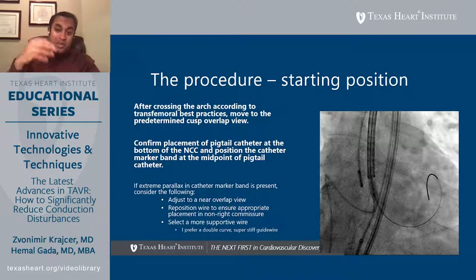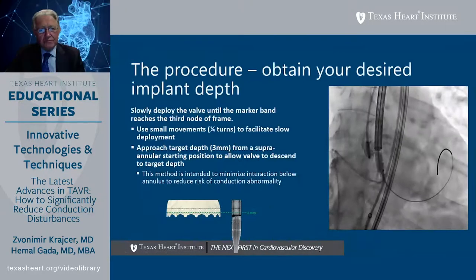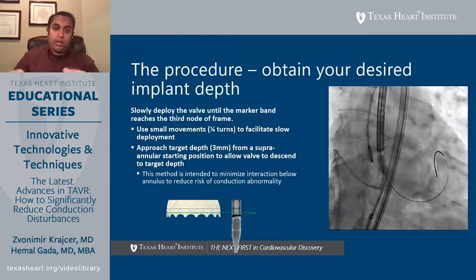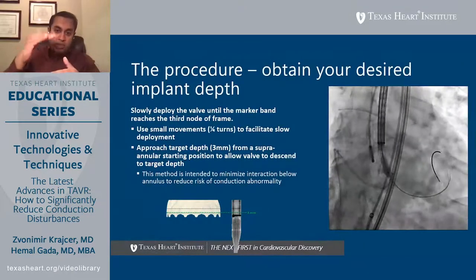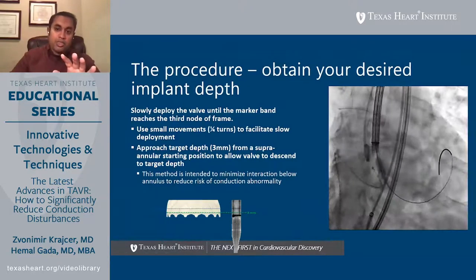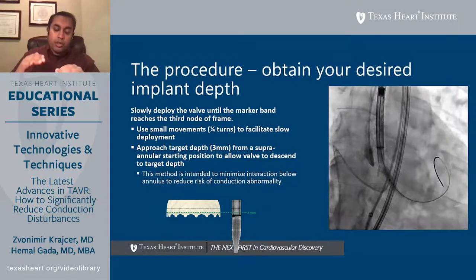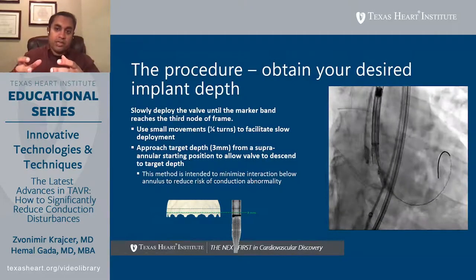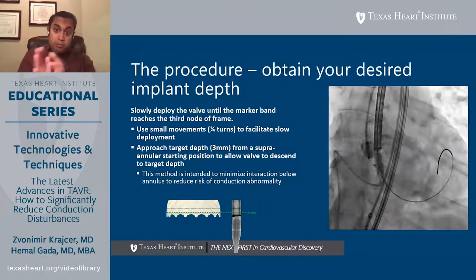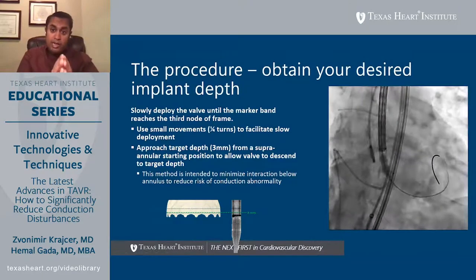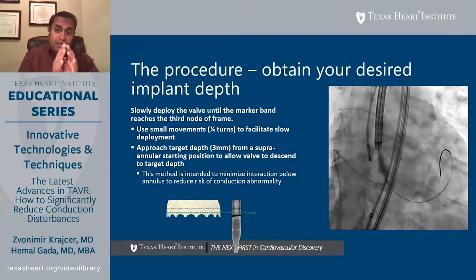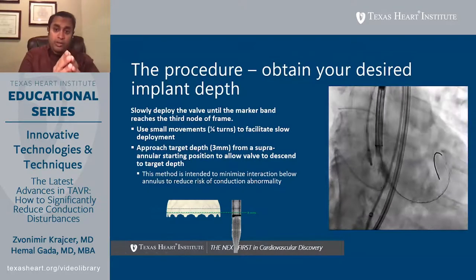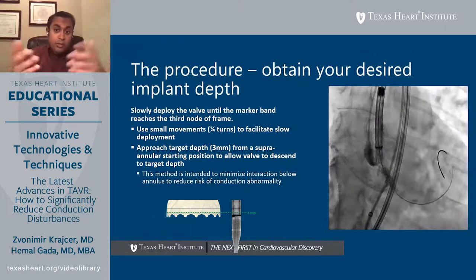So this is really a top-down deployment. We start with the marker band right around mid-pigtail and eject the valve down more ventricularly, as you'll see next. We slowly rotate the handle on the delivery catheter and the valve naturally starts its trajectory down toward the ventricle. This works because there's a centimeter of space between the nose cone and the valve housed in the delivery catheter capsule, and that capsule pins back the non-coronary leaflet quite well. If you've got a stiff wire in the non-right commissure, the capsule, and 5 millimeters of it below the ventricular plane—the annular plane—that's fine. You don't need more than that.